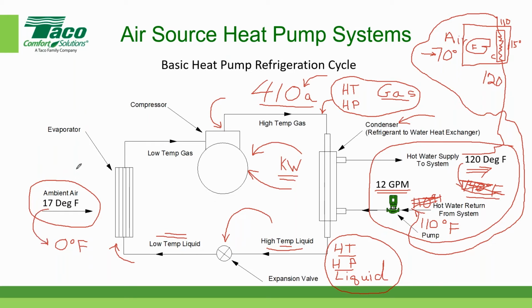So the refrigerant boils, and another name for boiling refrigerant is evaporation. Now the refrigerant evaporates and it absorbs heat from the ambient air, in this case 17 degrees Fahrenheit. Now, modern air to water heat pumps can extract heat from the ambient air as low as around -5 degrees Fahrenheit, which is amazing. The new technology that's out there today is just absolutely amazing.